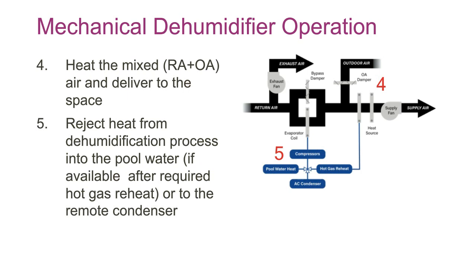Then you can reject the heat from the dehumidification process to heat pool water, because the evaporation load from the pool creates a little over 1,000 BTUs per pound that you need to handle. So most of the pool water heat comes from evaporation, and you can take that and put it back. You have to typically heat the air back up in those modes, unless you're in a space cooling in the middle, high season in summer, or you can send it to the remote condenser.